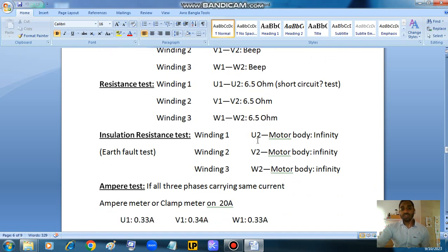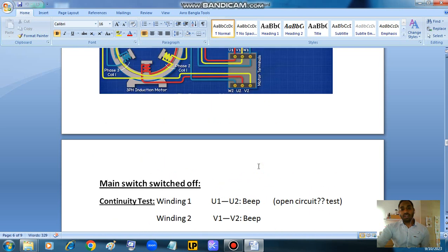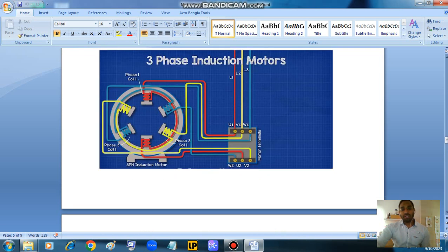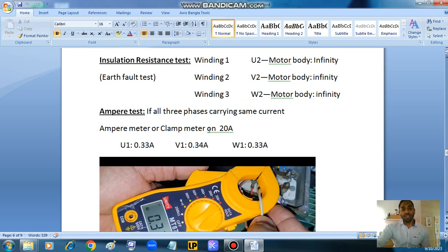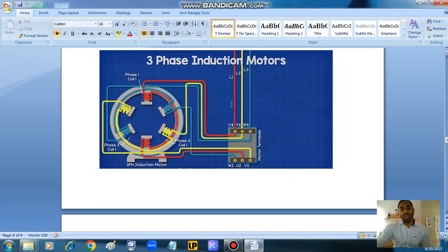And the third test, the insulation resistance test, you can do on any of the windings like this. At the motor terminal, you touch one probe of the multimeter to U1, V1 or W1 and to U2, W2 and V2, like one probe here or here, and the other probe on the motor body. There should be huge resistance, like infinity or many megaohms. Then the ampere test: to check whether all three phases L1, L2 and L3 carry the same current, you connect a clamp meter and check how much current they are taking.